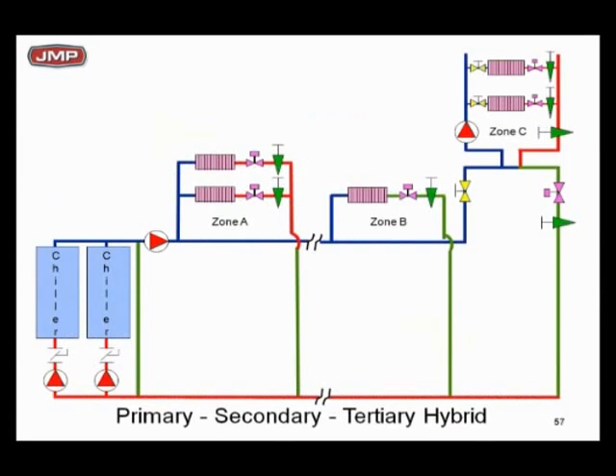Now here's primary-secondary-tertiary, or hybrid. Remember the pumping example showing how you isolate the high head loss zone — that's all we're doing here. Don't make the mistake of trying to put tertiary loops on every building if you don't need it. I've got primary loops with chillers and dedicated pumps at constant flow, that little green common pipe. I've got a secondary pump pumping zones A and B — there's plenty of head on that distribution secondary pump to pump zones A and B. Way out of the system I've got zone C with high head, so I'm going to isolate that zone with a tertiary pump.